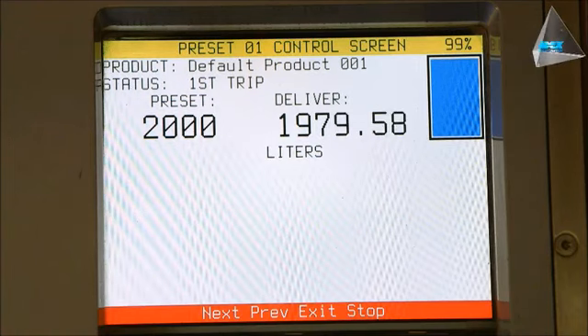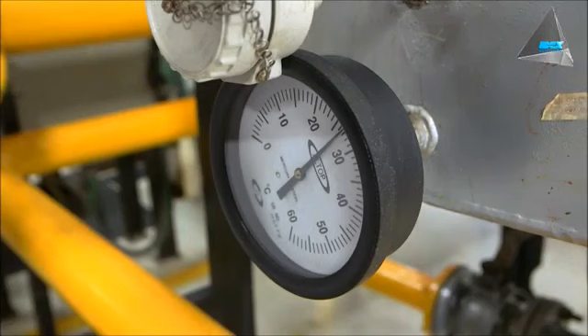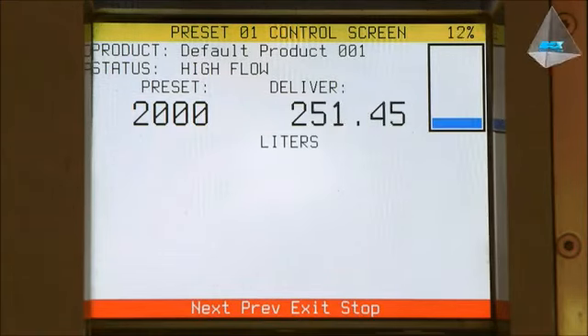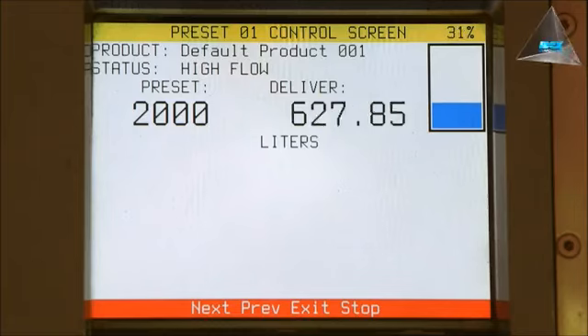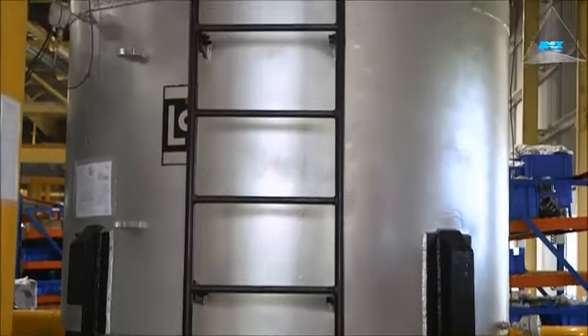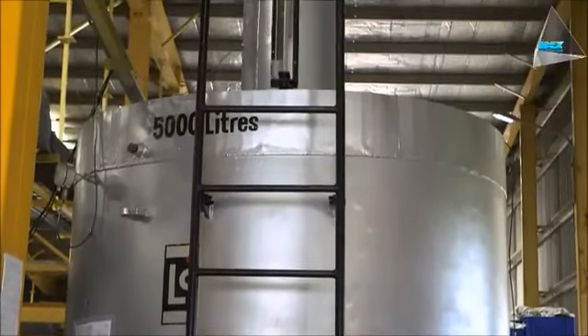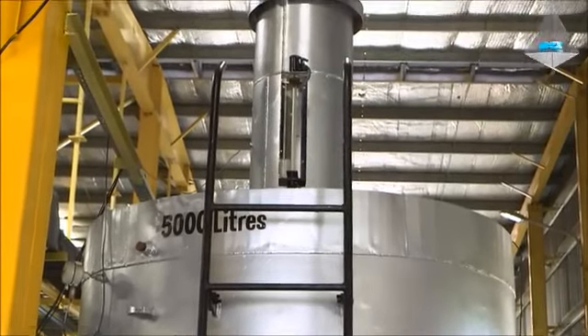Pass a quantity of liquid at a specific flow rate equivalent to the capacity of the prover. Record the temperature at the flow meter and the average temperature of the prover along with pressure. All the master meters will be calibrated against the LC prover using Calibest L as a test medium.